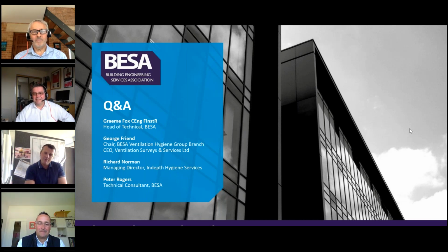You're right though, going back to the commissioning stage. That's the point where these problems can be caught initially, and unfortunately, quite often the commissioning documentation for the fire dampers doesn't align with what we're asking for in VH001. Too often it's a simple tick box checklist: Is damper accessible? Yes. Has damper been drop tested and reset? Tick, tick. No visual evidence. So we need to make sure that commissioning process is more robust, so we stop that being a problem when the building is handed over.